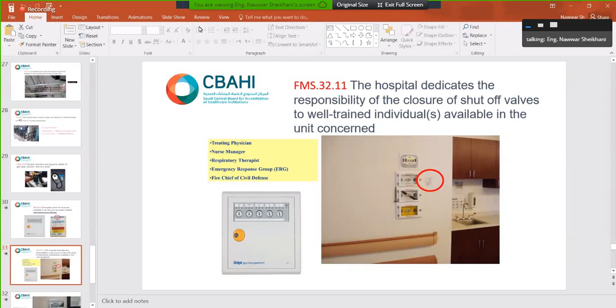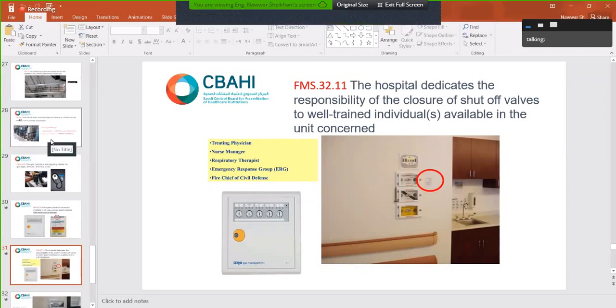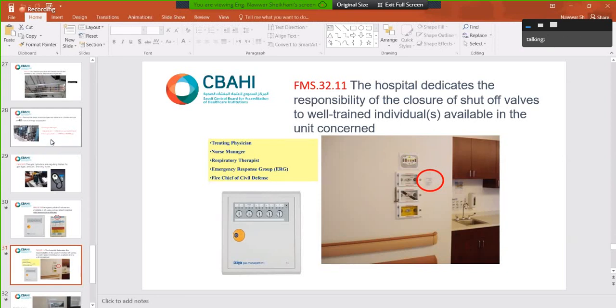Mr. Mohsen? Yes, thank you. There is another question regarding what is the time required for area valve leak tests and the frequency of testing of medical gases. Yes, for medical gas, PPM should be every 6 months. For PPM, it's 6 months. For testing of cylinders, with every batch you receive, you have to test one cylinder randomly. Hopefully this is clear.